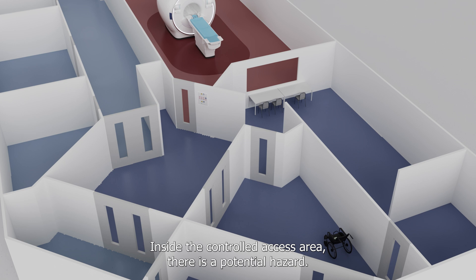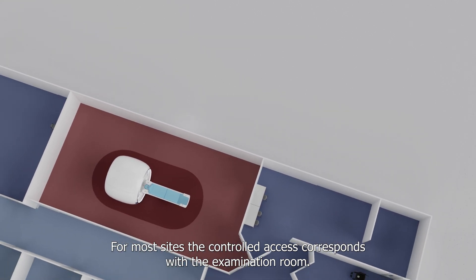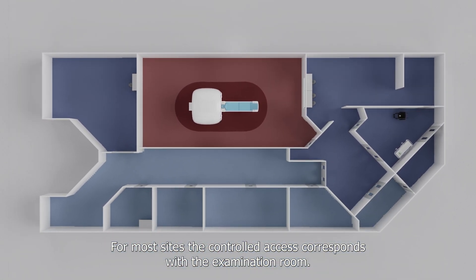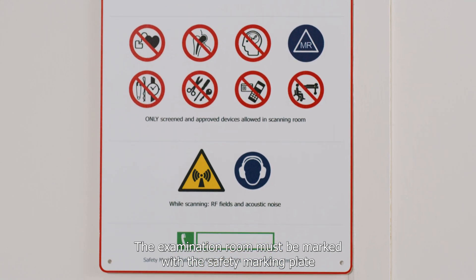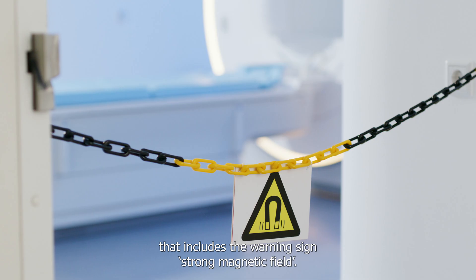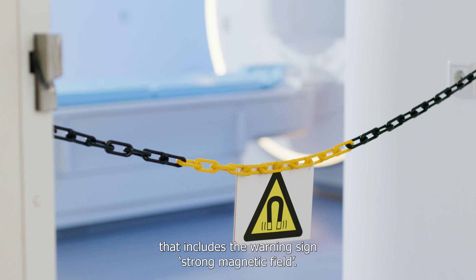Inside the controlled access area, there is a potential hazard. For most sites, the controlled access corresponds with the examination room.